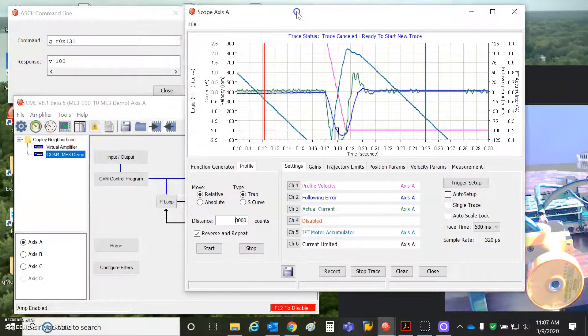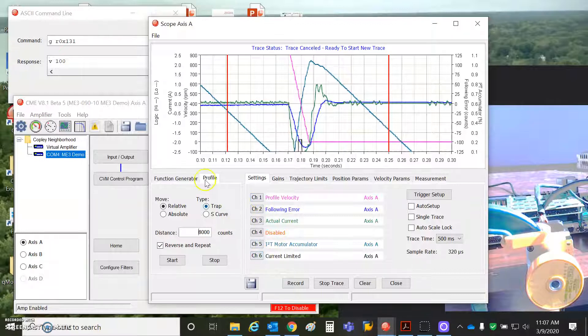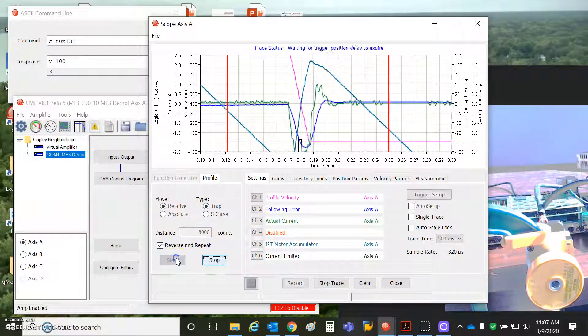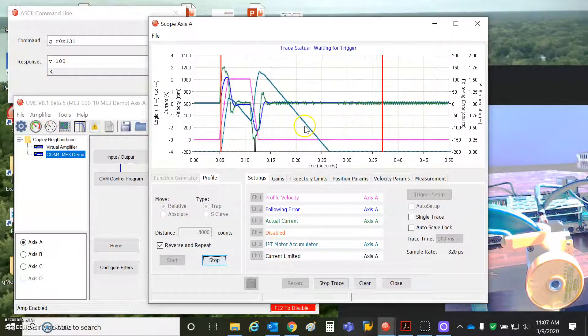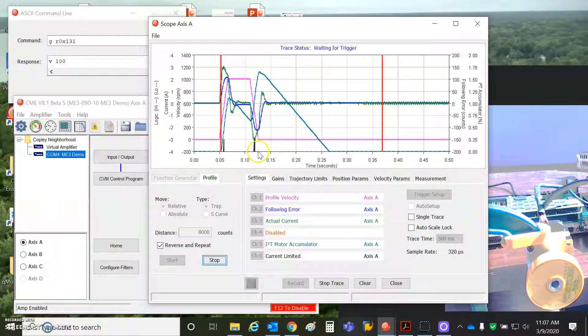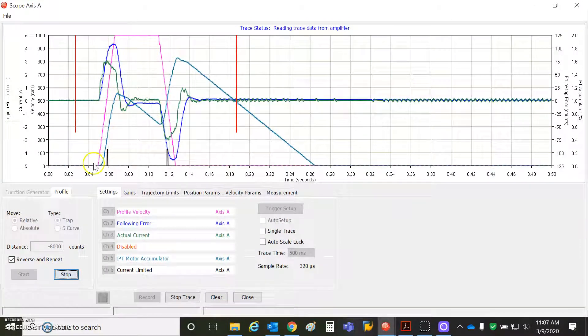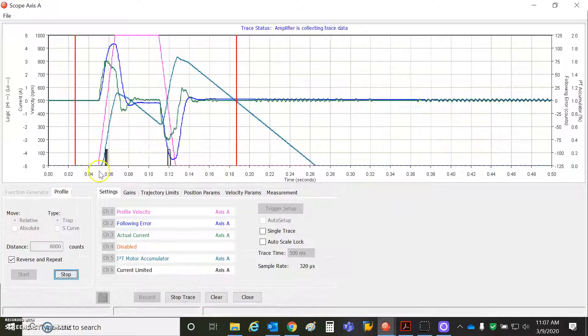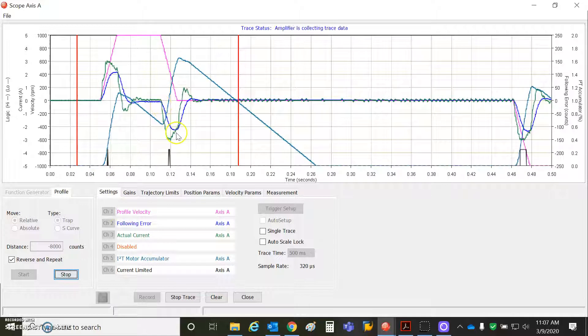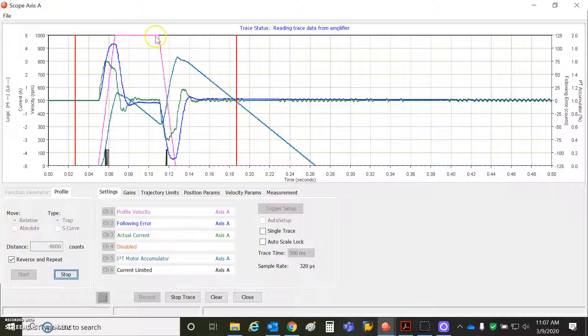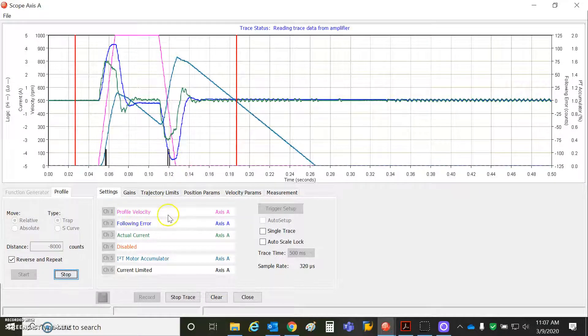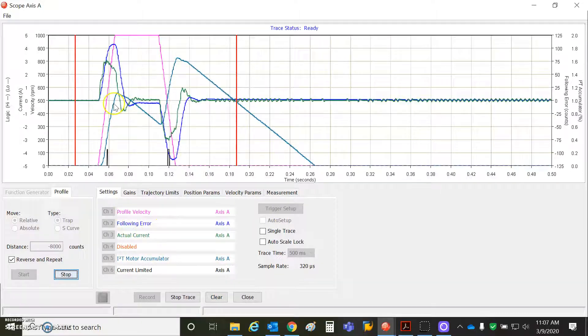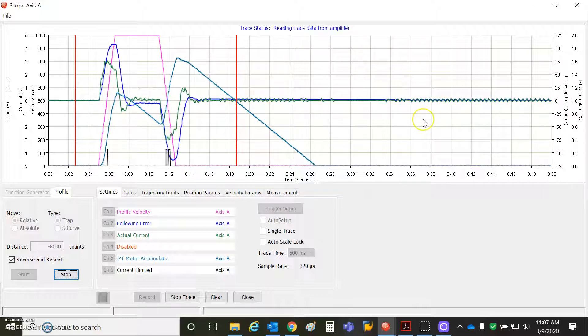Anyways, we're going to do some scope tracing here. And we're going to first look at making some moves back and forth. So I'm just doing some simple back and forth moves. We're going to break this trace down here so we can understand a little bit about what it's doing. So for this profile, I'm making a point-to-point move, and then I'm coming back. I'm accelerating, running at a velocity, decelerating, and stopping. That's in the profile velocity magenta. And you can see you get a little bit of a following error when you accel and decel, plus or minus, less than 100 counts.